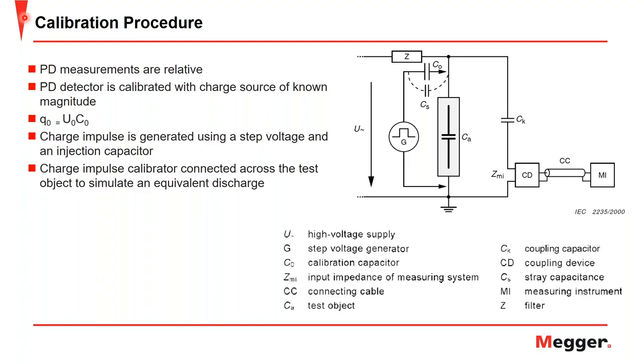Covering the calibration procedure, the partial discharge measurements are relative. So a PD detector is calibrated with a charge source of known magnitude, where that magnitude is the step voltage multiplied by the capacitance in series.